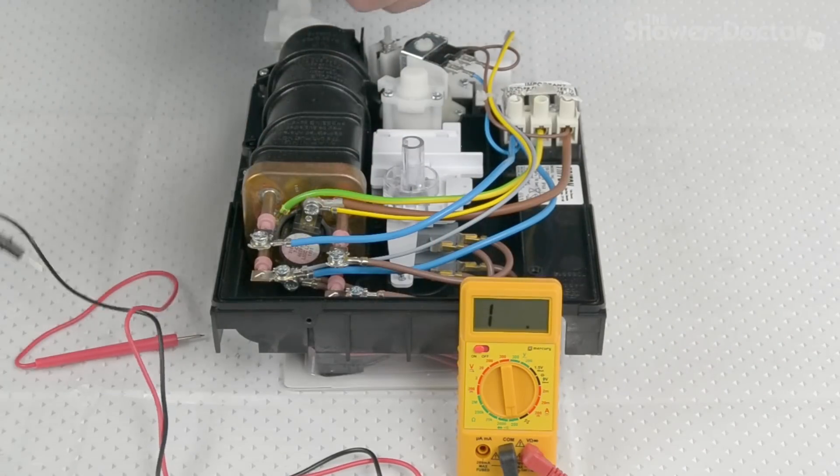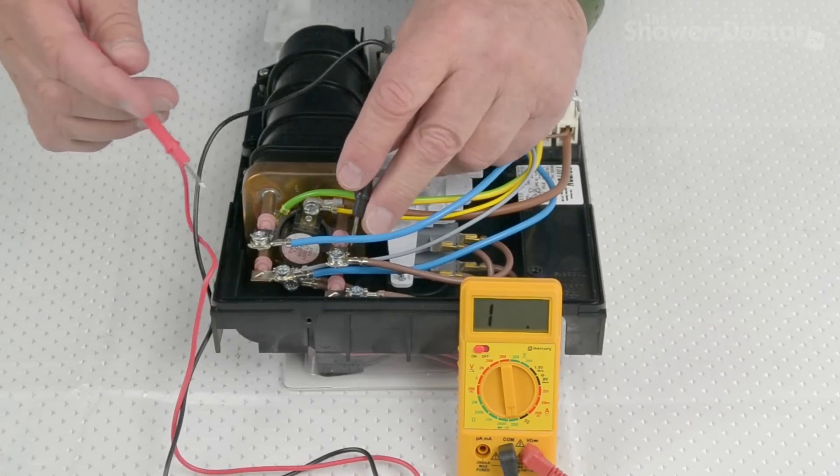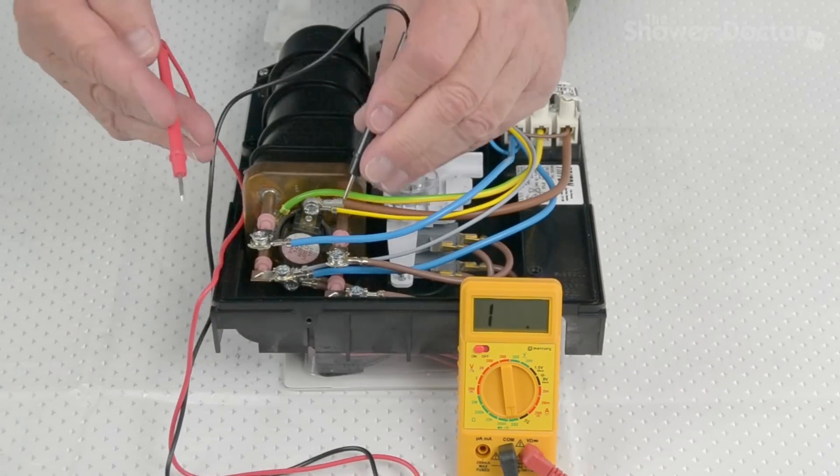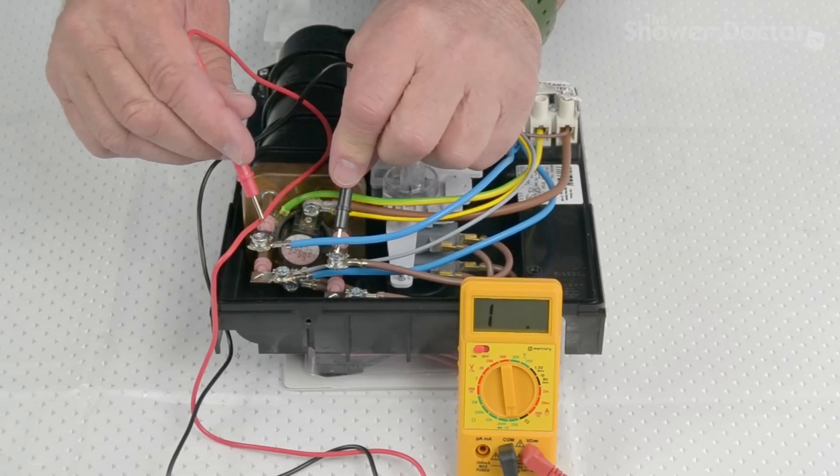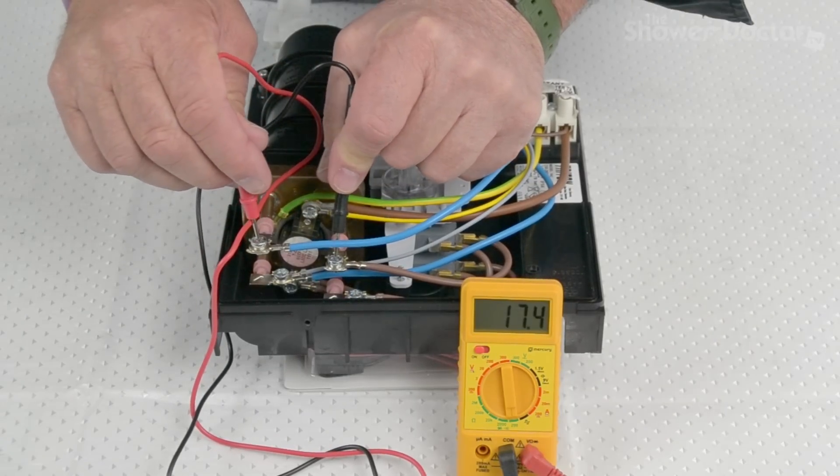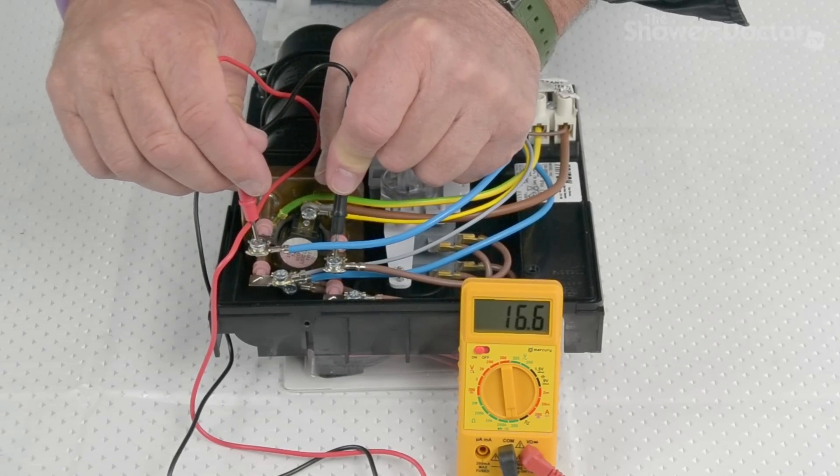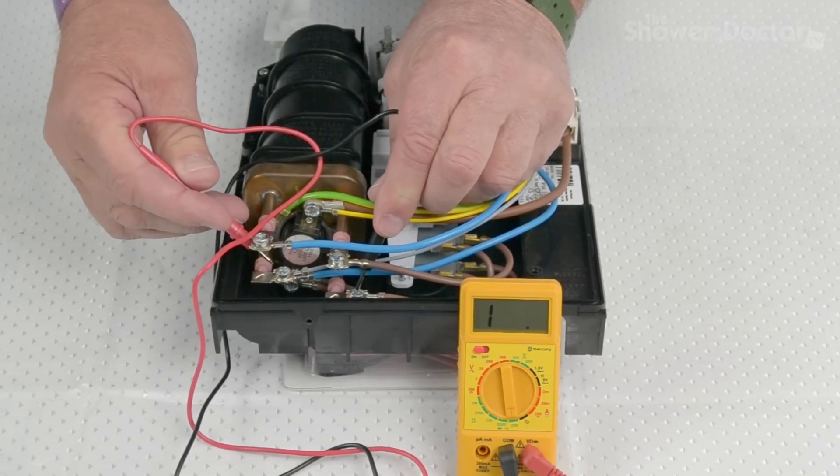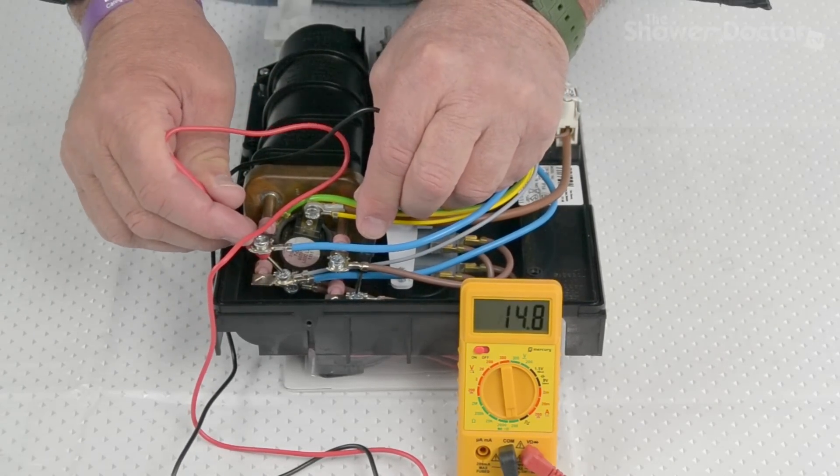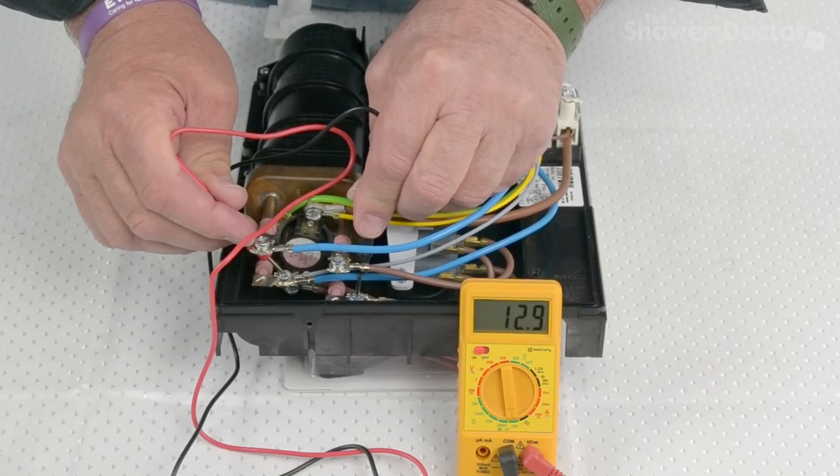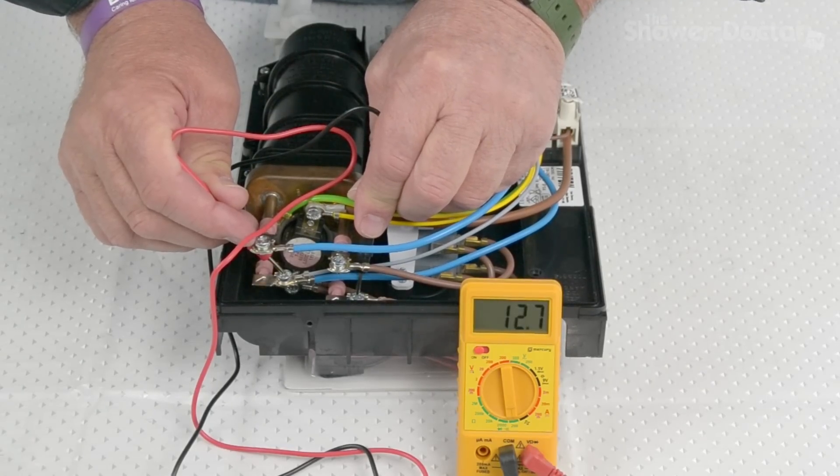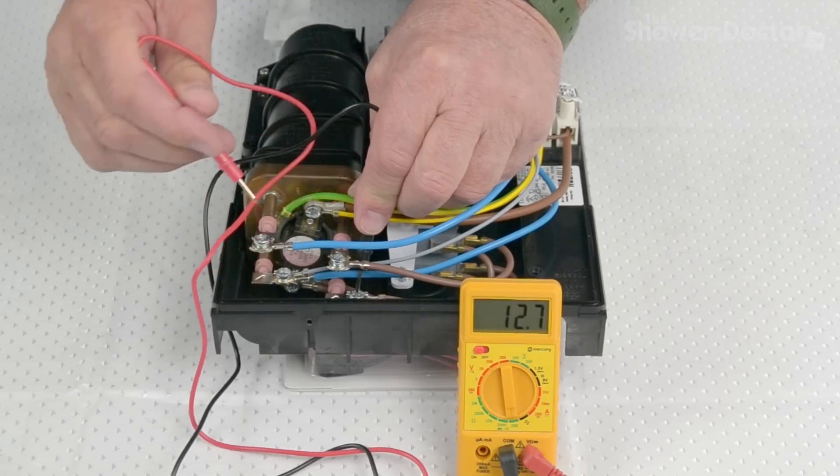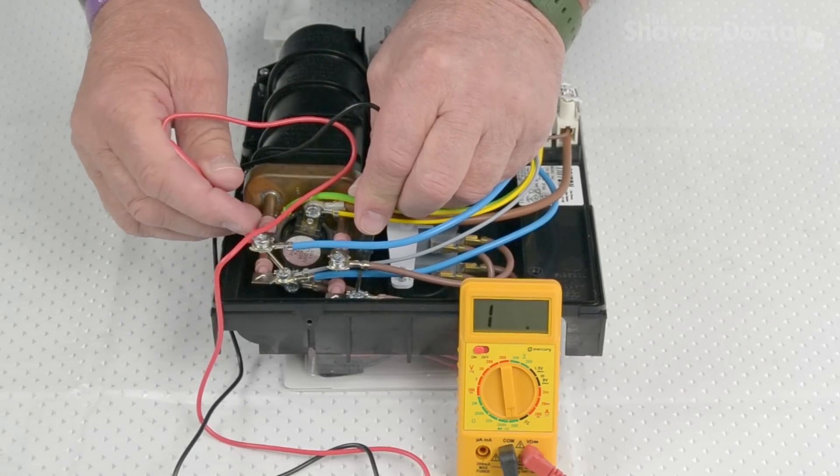And so once again, the polarity doesn't matter, but we're checking the resistance across the elements. So that's the live and the neutral. And in this element, we have about 16 ohms. And then down here, there's the other element. And we have, I don't know for this one, about 12 ohms for this one. So 16 ohms and 12 ohms, that's okay.